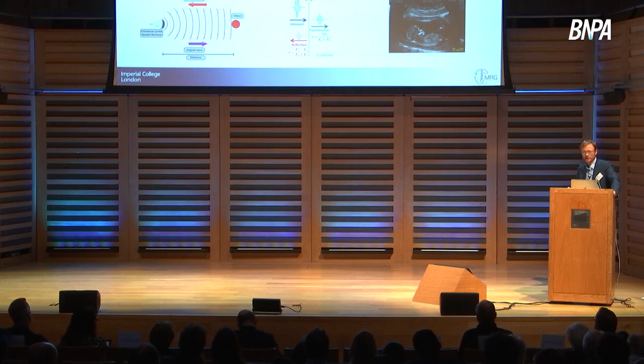Now, bone has a very high acoustic impedance, so almost everything is reflected. And that's why ultrasound is very good for imaging soft tissues like babies. Now, note that a coupling medium, such as a gel or degassed water, is needed between the transducer and the skin to avoid reflection at that air-skin boundary. So that's why you use this gel to allow transmission of the ultrasound waves into the body.